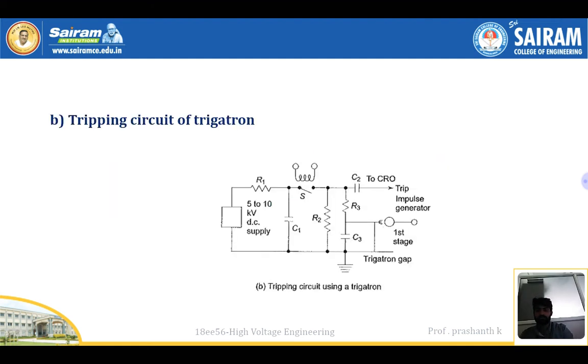Right. So this is the tripping circuit of the trigatron. See here, there is a tripping circuit consisting of a trigatron, this one. There will be a switch present, like a relay switch. Likewise it is made, and we are giving a 5 to 10 kilovolts DC supply. Then R1 is the current limiter, and also C1, C2, C3 will be there for charging and also give the specified voltage, specified output, to trip the impulse generator and the first stage trigatron gap.